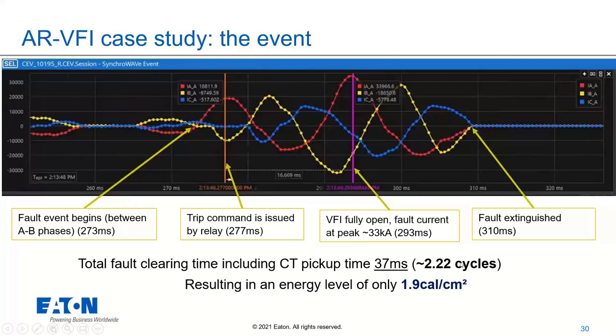The device that we were using, the vacuum interrupter itself, is one of the fastest on the market, but that's a two-cycle device. So we've got all the sensing and relaying down to about a quarter cycle there, which is extremely fast. And that's going to result in an energy of about 1.9 calories per centimeter squared.